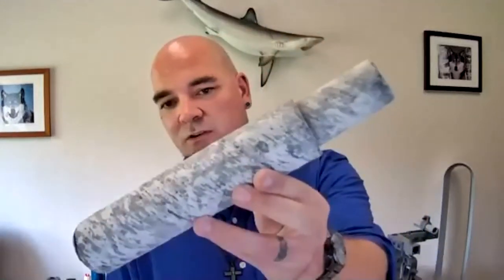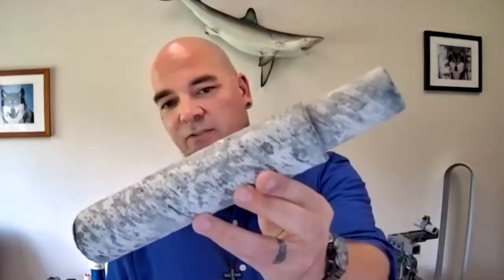We do manufacture a complete conduit system, 3/4 inch through 12-inch, with UL listings for 3/4 through 6-inch. Our UL listing is UL 2420 for below ground, 2515 for above ground. We do have an NFPA 130 phenolic conduit, which is this conduit right here. This is an example of that. When it's tested at UL, it's burned for 2 hours at 1850 degrees on a firewall. And this is an example of what it would look like after it's been charred for that amount of time. It also faces a 30 PSI hose down test directly thereafter to make sure that these systems remain functional.